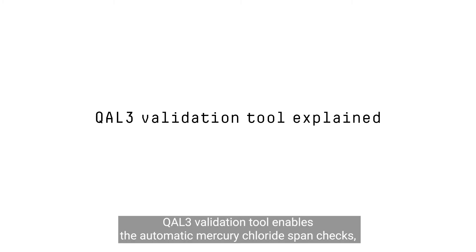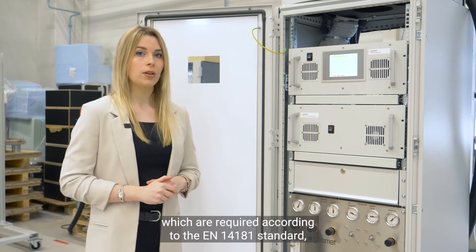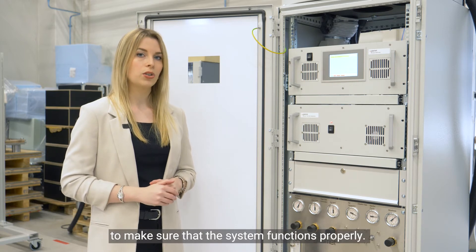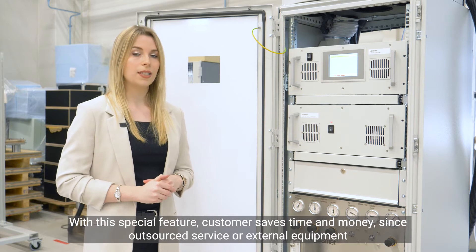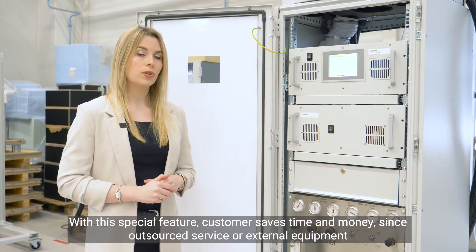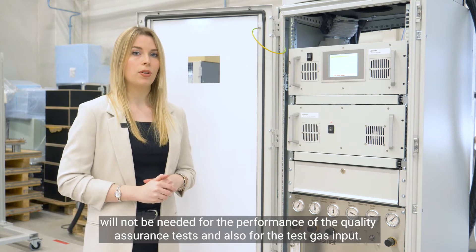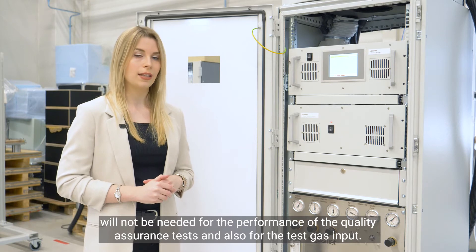The QAL3 validation tool enables the automatic mercury chloride span checks, which are required according to the EN 14181 standard to make sure that the system functions properly. With this special feature, the customer saves time and money since outsourced service or external equipment will not be needed for the performance of quality assurance tests and for test gas input.